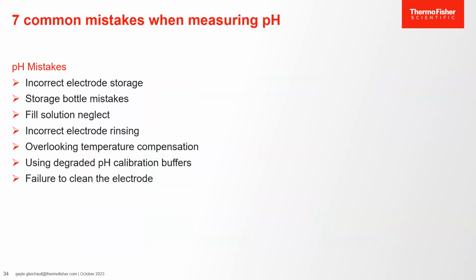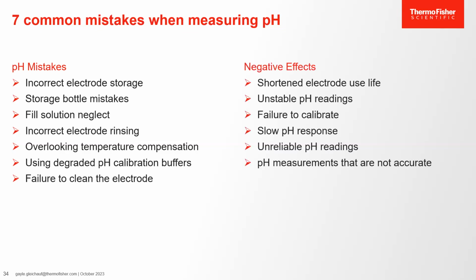Briefly, here are 7 common mistakes that are made when measuring pH. They include incorrect pH electrode storage, storage bottle mistakes, fill solution neglect, incorrect electrode rinsing, overlooking temperature compensation, using degraded pH calibration buffers, and failure to clean the electrode. These negative effects can occur due to the mistakes. They are shortened electrode use life, unstable pH readings, failure to calibrate, slow pH response, unreliable pH readings, and pH measurements that are just not accurate.